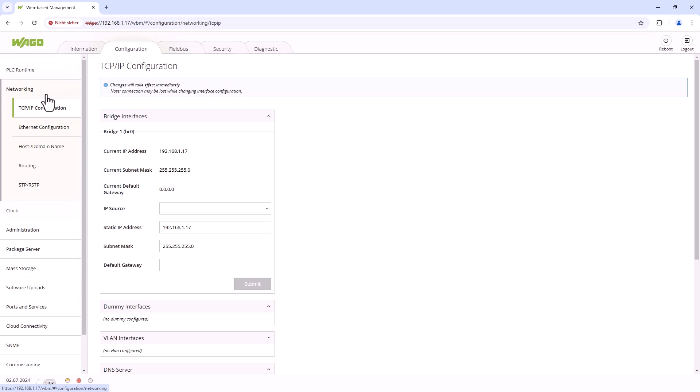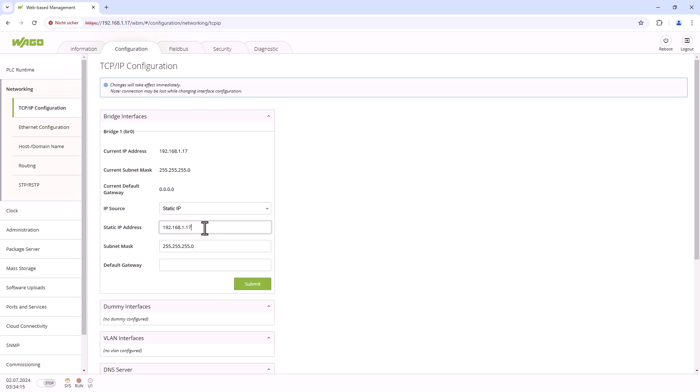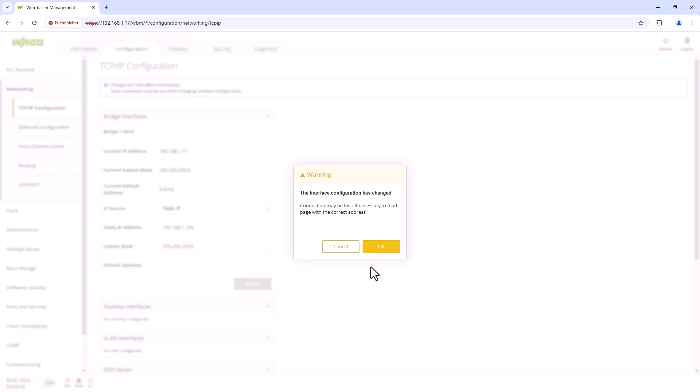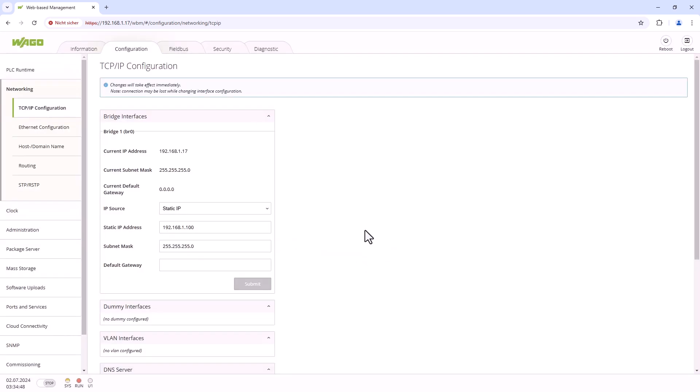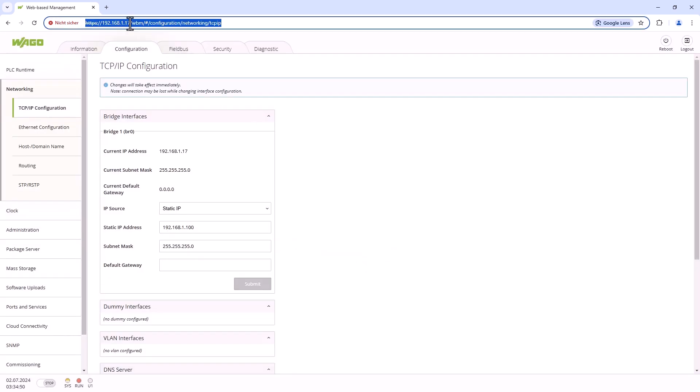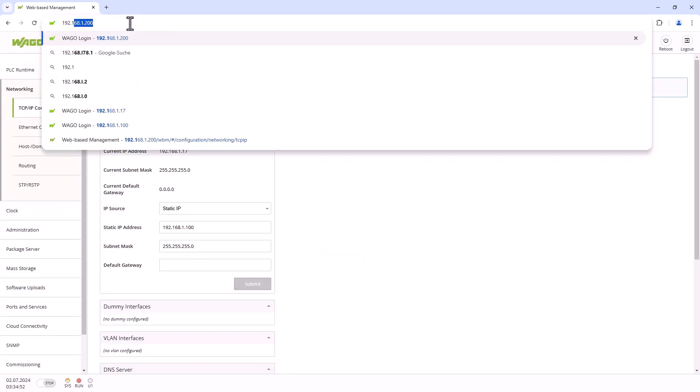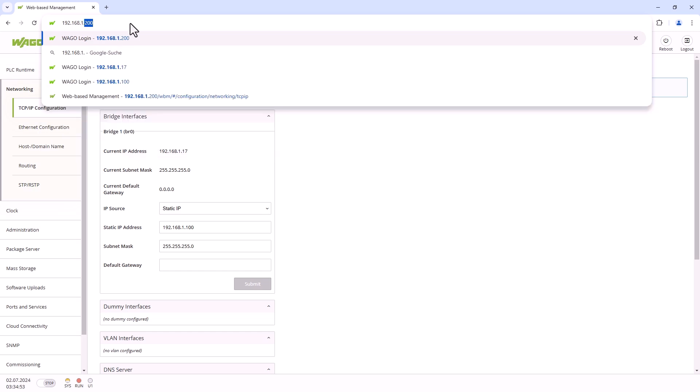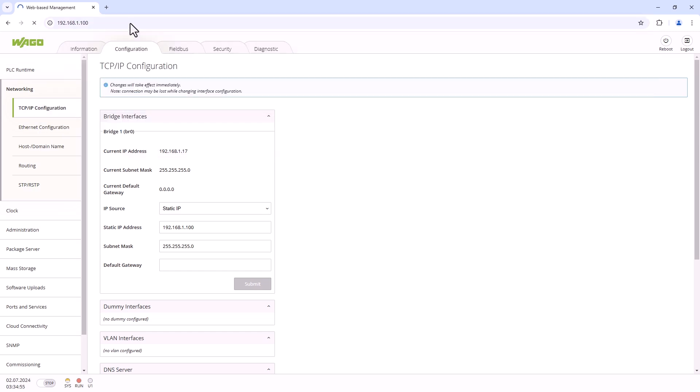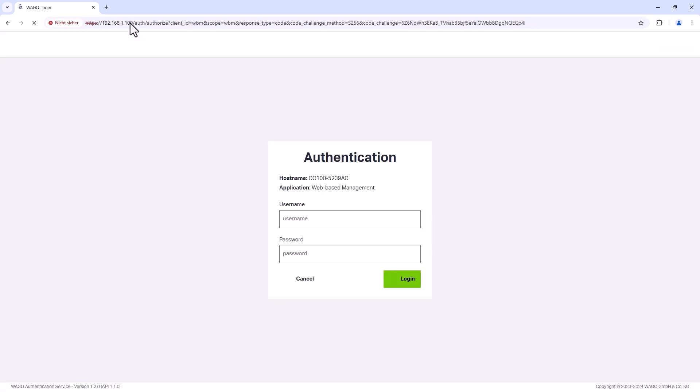It is important to note that the temporary fixed IP address is always 192.168.1.17 and is only active until the next reboot. Therefore, this address is not suitable for installing an application as the controller will be rebooted during the installation process and will no longer be accessible. In this case, you should first use the fixed IP address function to assign a correct static IP address, which must not be 192.168.1.17 again, and then install the application. This fixed IP address mode is also available for most WAGO controllers.